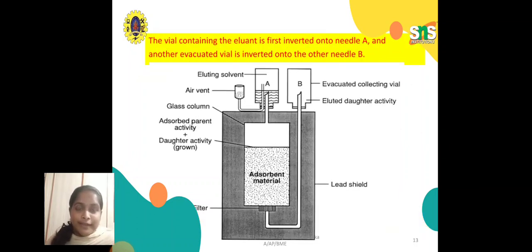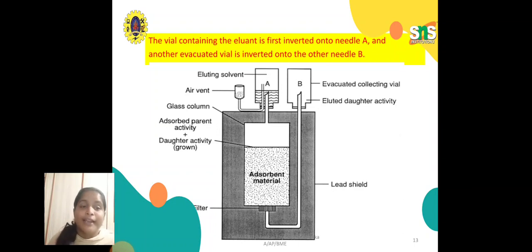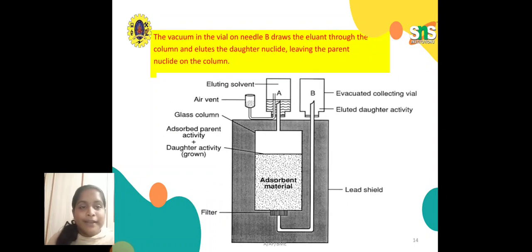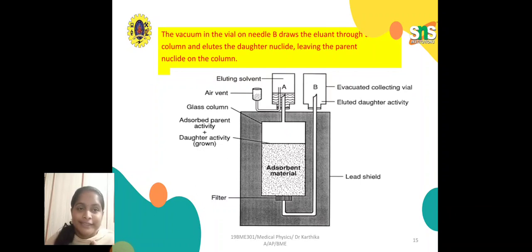The vial containing the eluent is first inverted onto needle A and another evacuated vial is inverted onto needle B. Needle B contains the evacuated collecting vial for the eluted daughter activity to reach its equilibrium condition. The vacuum in the vial on needle B draws the eluent through the column and elutes the daughter nuclide, leaving the parent nuclide on the column. This action can be repeated until the daughter nuclide reaches its equilibrium condition.